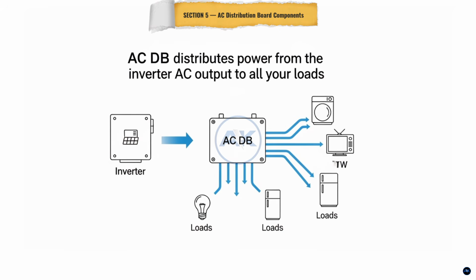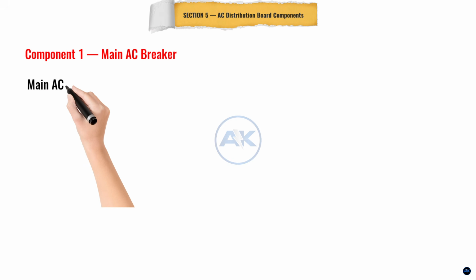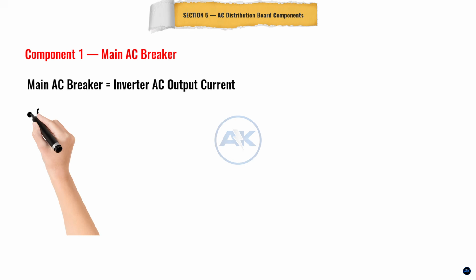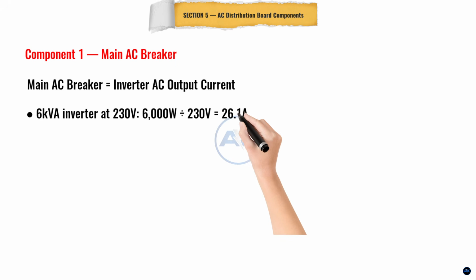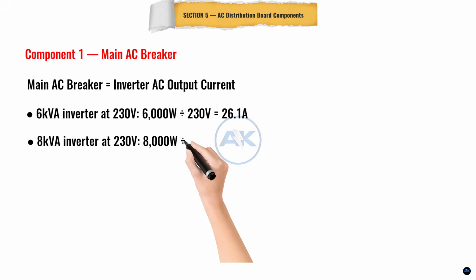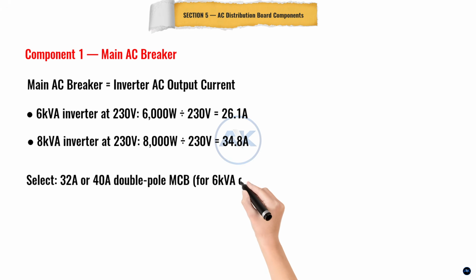Section 5B. AC Distribution Board, Components and Calculations. The AC distribution board takes the output from the inverter and distributes it to all your loads through individual circuit breakers. Each circuit needs a breaker that protects the cable and the appliance, not just any size will do. The main breaker is sized to the inverter output. For a 6 kilowatt inverter at 230 volts, the output current is 26 amps. We use a 32 or 40 amp double pole MCB here.